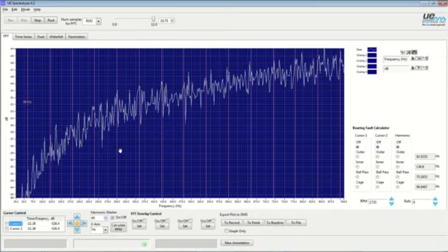So this spectrum, knowing the voltage, I know there will be corona present. So I expect 60 hertz peaks. I also expect, due to the ionization process, the abundance of frequency noise in here. That says it's electrical in nature, but it doesn't tell me the type of fault.